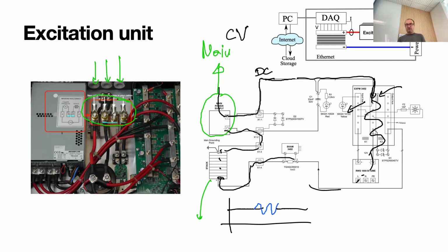There is one issue that is happening also here in Dijon. It happens with us all the time. Although you're operating in CV mode, it might happen that when you start up the circuit, there is one fault. There is a voltage here from the stack and voltage here of the power supply unit. And it might happen that this voltage is bigger than the one of the power supply. When you started, the power supply is 0 volts. This means that the polarity here will reverse and our electronics goes into safe mode.